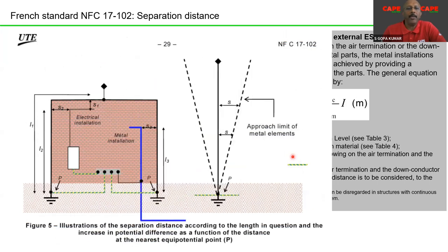In the NFC standard, you can also find this kind of a picture. What does it mean is, the down conductor, you keep equipotential bonding at the bottom of the building, and you see here the air terminal and the down conductor, separation distance S, approach limit of metal element. That means the metal elements of the building must be this much distance S away from your building. The same technique of IS IEC 62305 is included in NFC 17102.